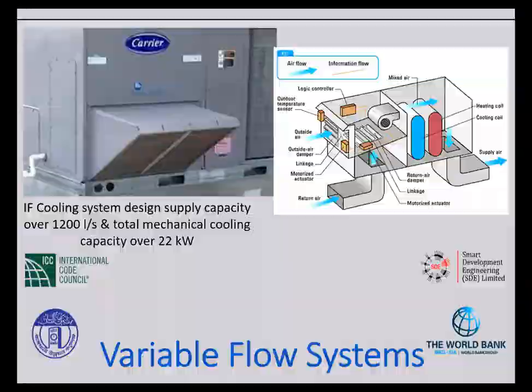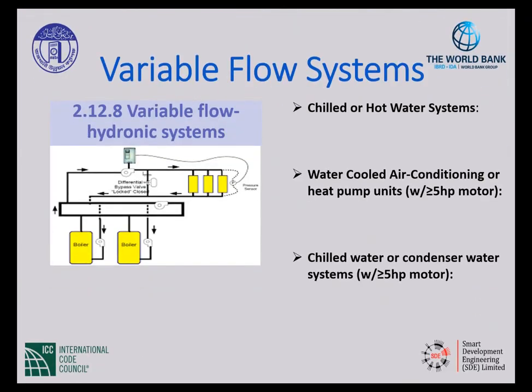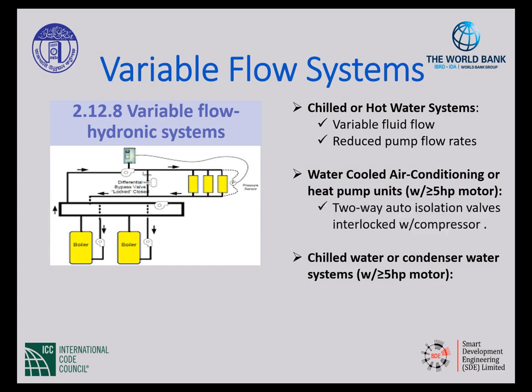All right. Then we're talking about some variable flow. So it talks about chilled or hot water systems have to be designed for variable flow and capable of reducing pump flow rates to no more than the larger of 50% of the design flow rate or whatever the manufacturer specifies. That's for chilled or hot water systems. Now, water-cooled air conditioning or heat pump units with a circulation pump that's bigger than 5 horsepower has to have a two-way automatic isolation valve on each water-cooled air conditioning or heat pump unit, and that's interlocked with the compressor to shut off the condenser water flow when the compressor isn't operating. It's, again, just controlling those times, shut things down when they're not needed.